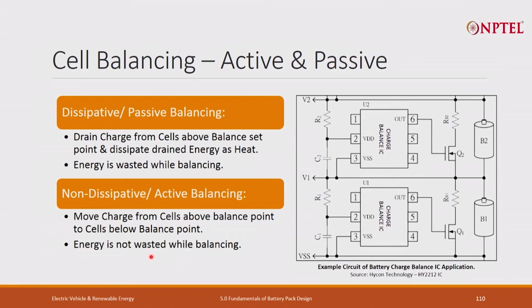It's impossible to have zero balancing, zero differential voltage. Then you limit, okay, 5 millivolt, 10 millivolt, 20 millivolt, more than that I will not allow, I'll allow balancing to happen. If it is within the 20 millivolt, I'll say no balancing is required. In the active balancing, energy is not wasted, but yes, it can impact the cell life. So here is the application, how it is being done. You try to understand. Any question, you can write us back.